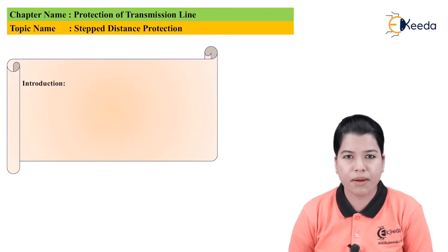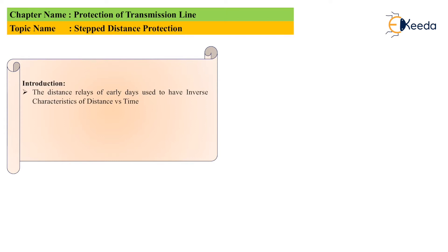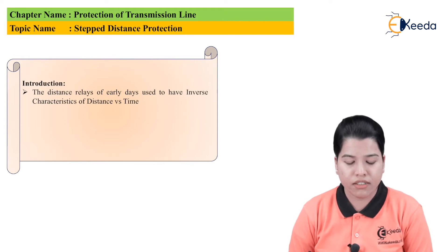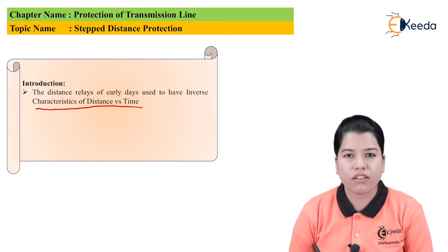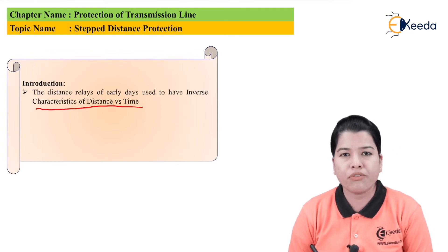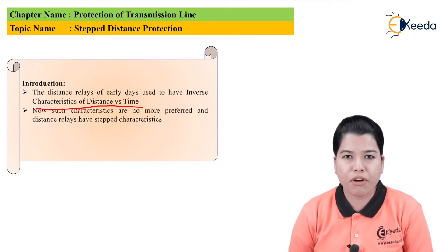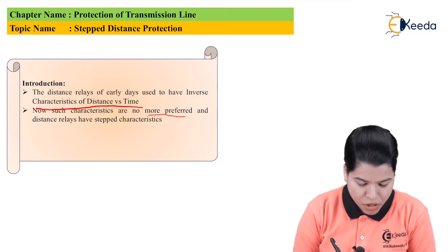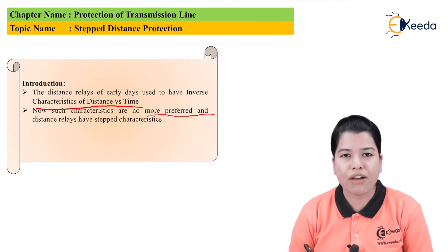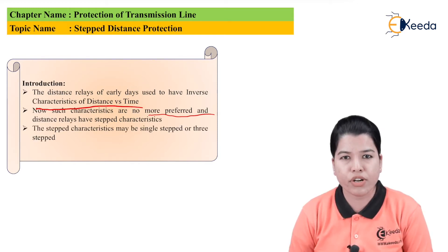Let us study the introduction to the stepped distance protection scheme. The distance relays used earlier had an inverse characteristic of distance versus time. The meaning of inverse characteristic is that as the distance goes on increasing, the operating time goes on decreasing. But such characteristics are no more preferred, and these days distance relays have the stepped characteristic. The stepped characteristic used for stepped distance protection comes in two types: single step and three step protection.